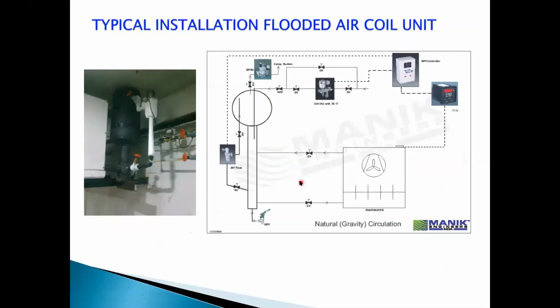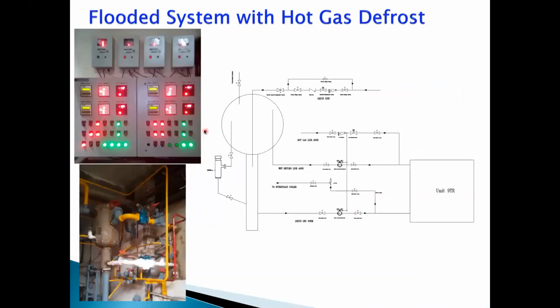This is a typical application of a gravity feed system. The gravity feed system is the most popular system in India. It has been there for more than 40 years, 45 years now, in India. It is used in different applications and different locations. We have this cold storage room with a float control and solenoid valve, which typically operates depending on the level in this coil, so the liquid will be maintained. We can implement hot gas defrosting.